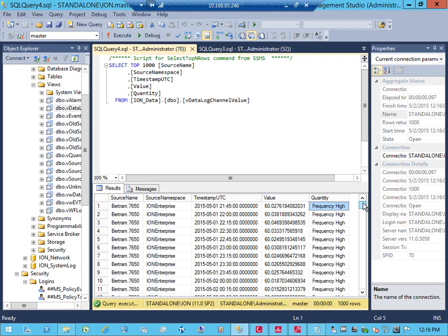Now, when you think of that bank of 32 registers in the module, they are corresponding to the first column of your query. So when you construct your query, you really need to pay attention to what you're querying. If I were to query all this information, I'm not going to use anything that's outside of the first column. And if I query more than 32 rows, I'm querying more than I can expose to that module. So that's the first two sets of constraints in both row and column to consider.